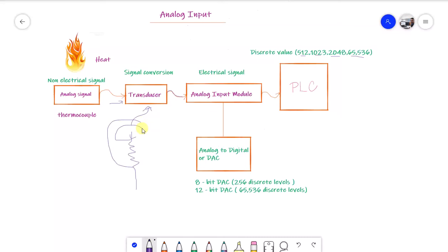Even in this case we will use some converter for isolation purposes. If something goes wrong in the shunt, it should not destroy the analog module itself or the PLC module. For that purpose, we will use isolation converters in between the analog input and external devices. If you have an electrical quantity that itself meets the requirement of the analog module, you can connect it directly.